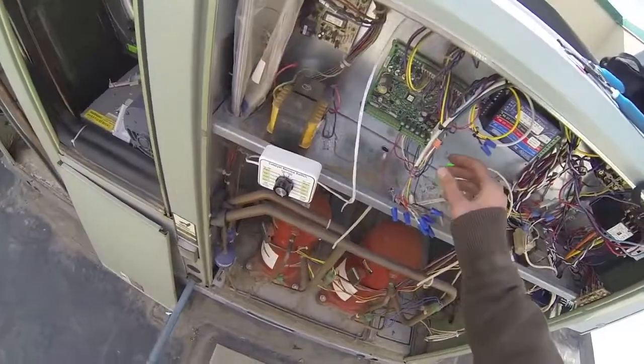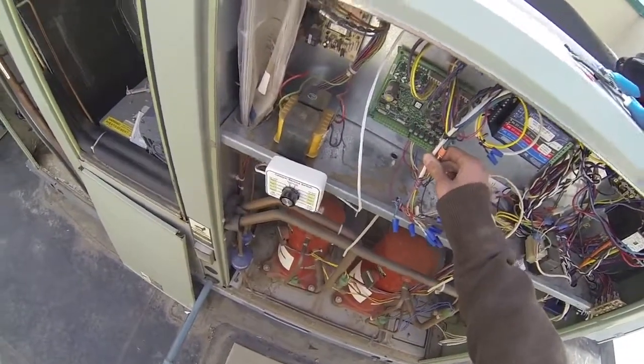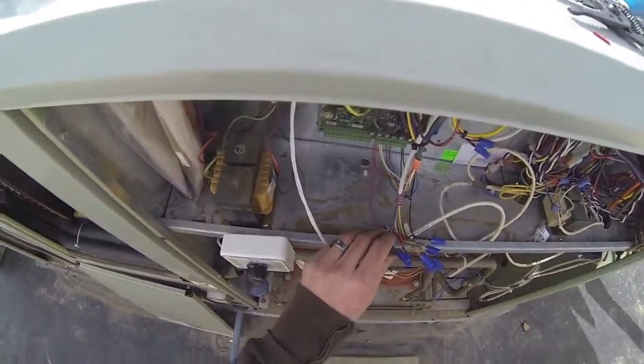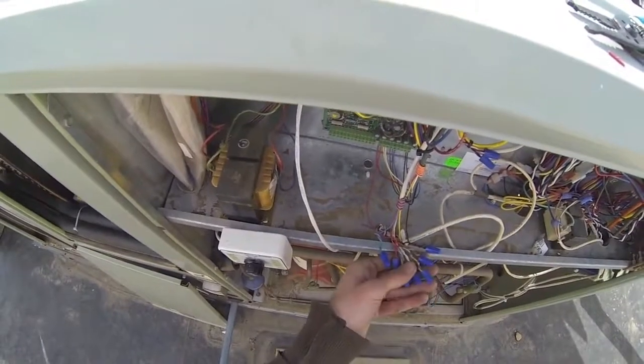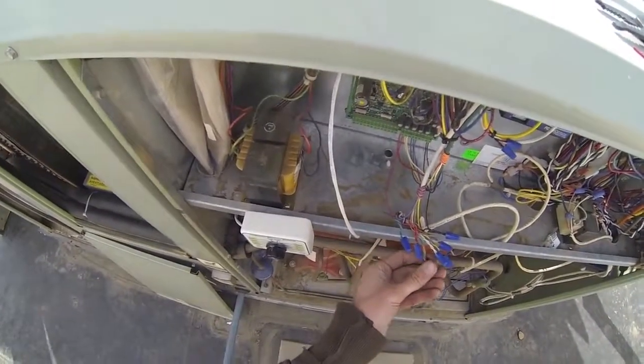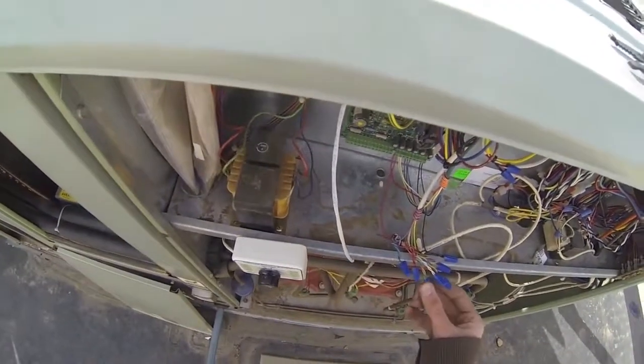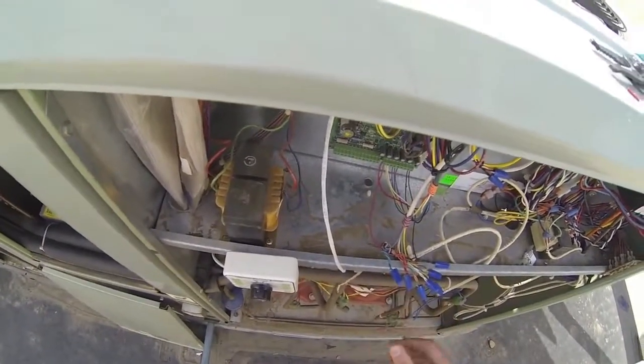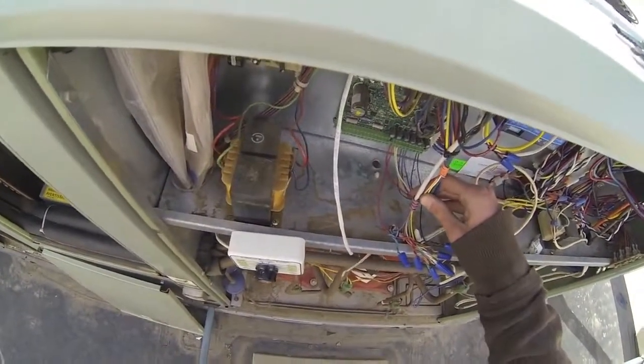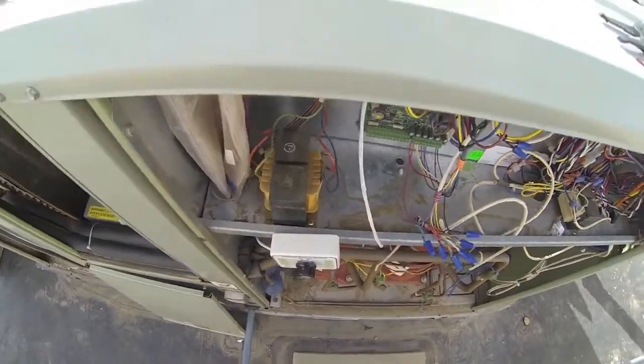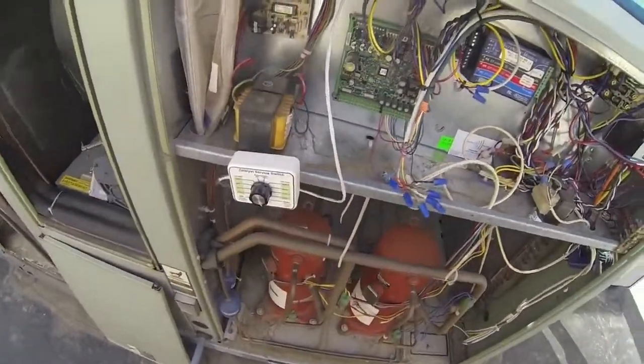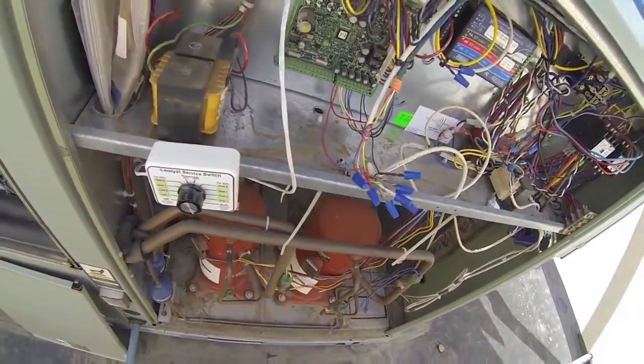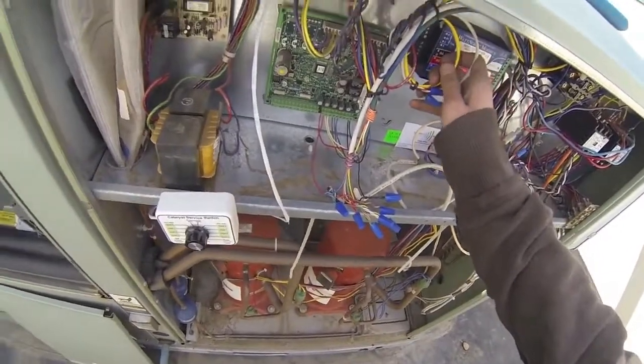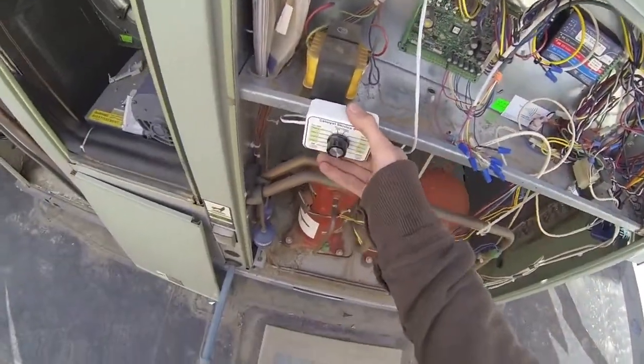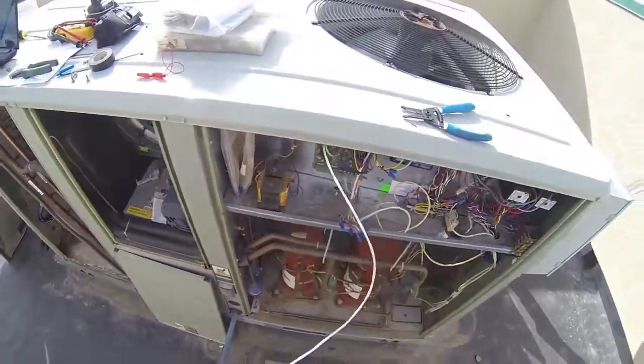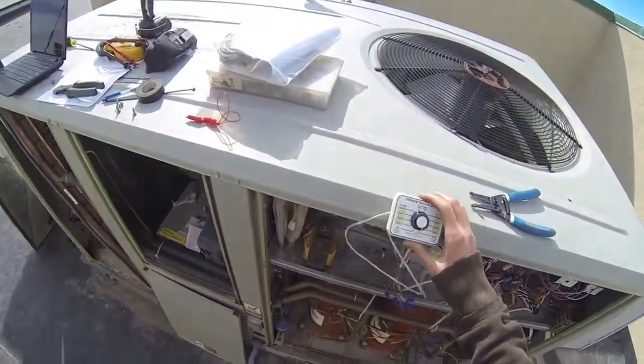And then we, with our 8 conductor white, we cut into the thermostat wires where their existing calls are coming from. We make sure that we double up our fan with the occupied, and then we land our low voltage controls onto the RTM board. And then we're able to wire up the service switch with our yellow 2 conductor. We make sure we leave enough slack in there so we can pull it out and use it or set it anywhere that we'd like.